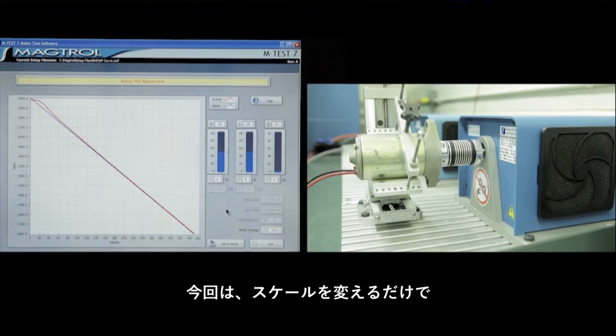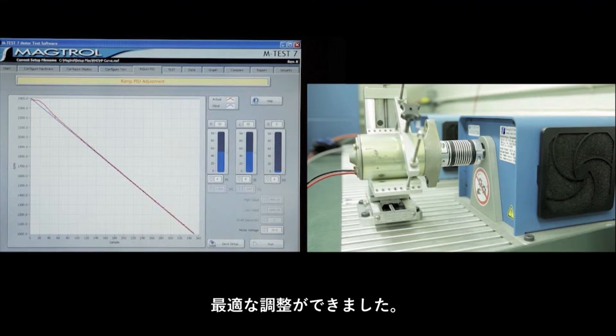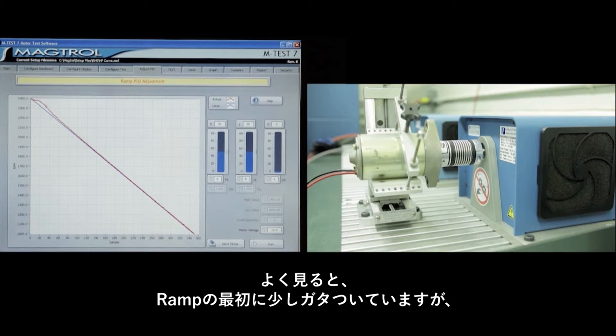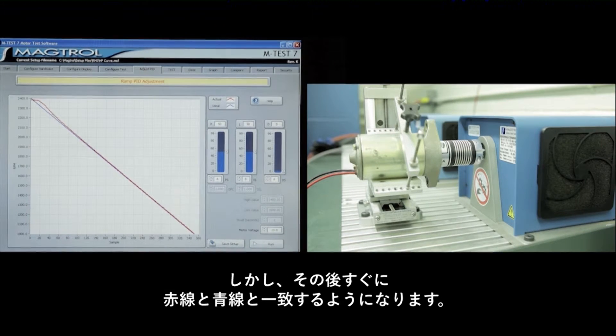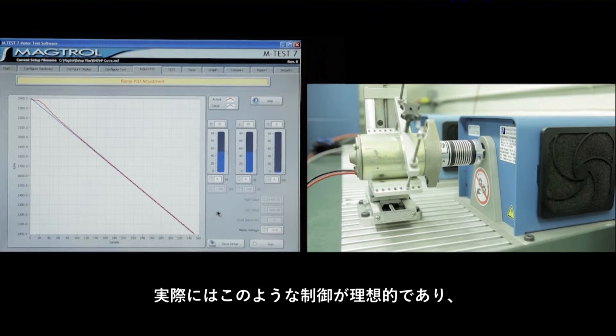We'll go to the next scale of B and run the procedure again. Now in this case, just changing the scale gave us a very nice adjustment. There is a small amount of what is called a jerk at the start of the ramp, but the red line comes in and lays on top of the blue line for the rest of the way down — this would be pretty much an ideal adjustment.